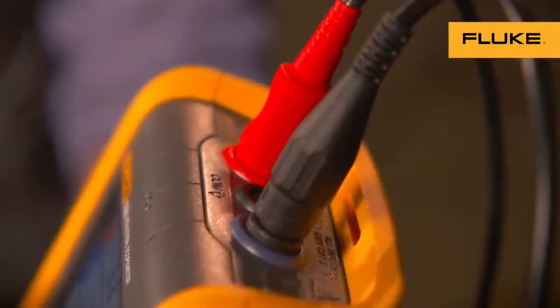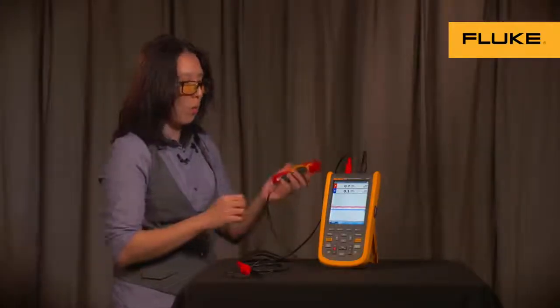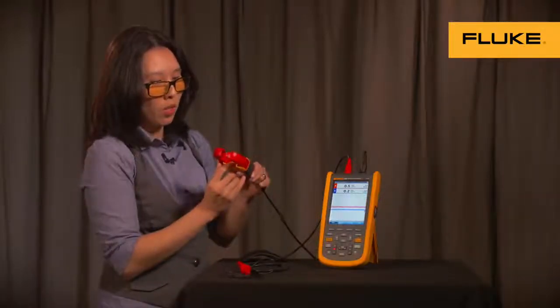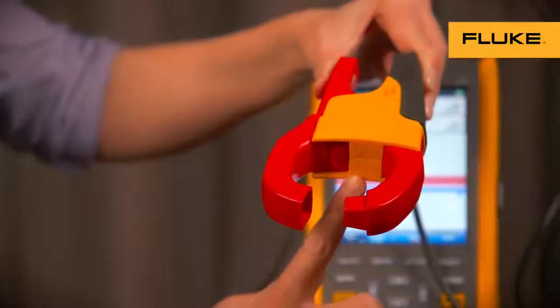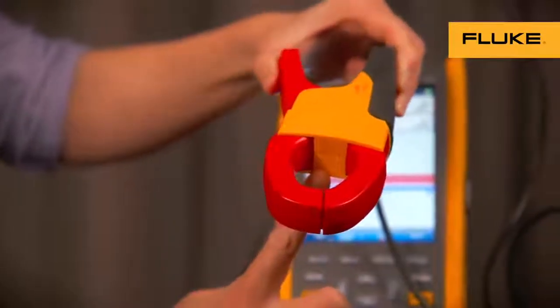Now you can hook your AC current clamp up to the instrument and clamp on to your current source. And keep in mind, when you're clamping on to the current source, this arrow right here on the inside, make sure that it's pointing towards the load.